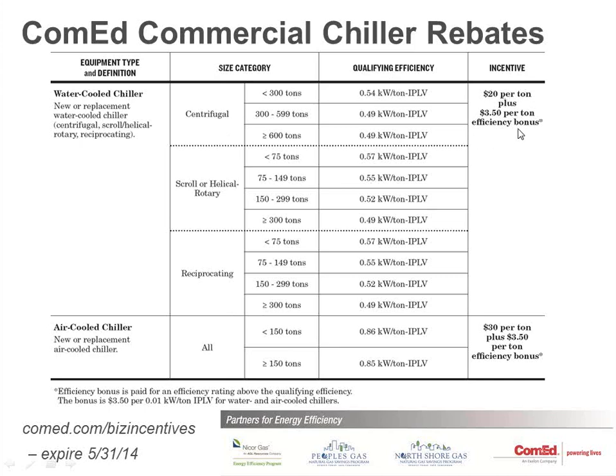So if you put in something that was a screw machine that was, say, 300 tons, you got to be 0.49. If you put in one that's, we'll say 0.39, just to make the math easier, right? So that gives me a $35 bonus. So that would be a $55 per ton rebate I would get on that machine. And it would be the nominal tonnage, not the application tonnage, but the nominal tonnage is what you have to use on these. You also have to use the IPLV at the nominal tonnage rating, not your specific project rating. So that's important to note. And if you don't know what IPLV is, that's the part load efficiency. So full load efficiency is irrelevant.